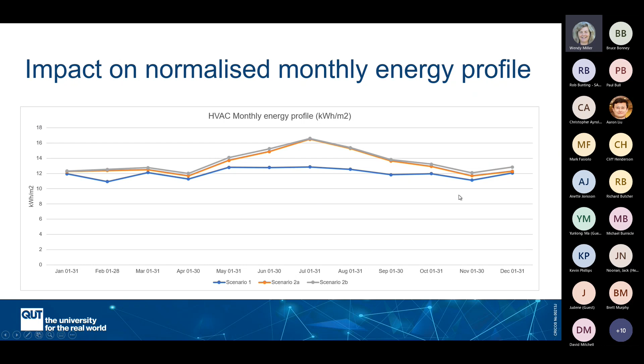Despite this, however, the impact on summer peak demand is also significant. So on a hot summer's day, running this ward at 100% outdoor air will increase the peak demand in kilowatts, the electrical load, by about 180%. This is particularly important if a site is paying demand charges.